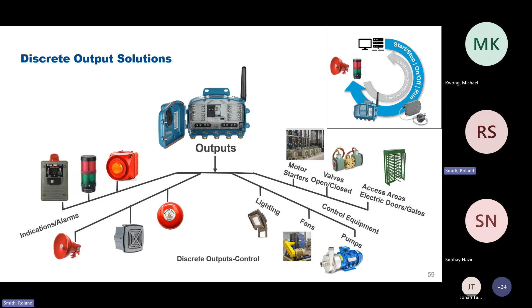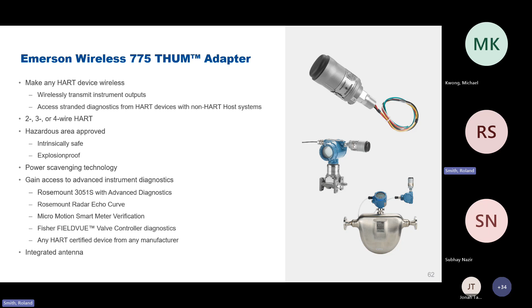We do have online corrosion and erosion monitoring, and a little bit on the THUM product. So a THUM is available as an option where a customer may have a traditional 2-wire loop-powered pressure transmitter, for example. We can install a THUM. It's loop scavenging, and we'll pull the HART variables off of that particular device, including diagnostics in some cases, depending on the device, and send it back to the gateway as well. So stranded diagnostics, radar curves, initiating some of our fancy things we do with Coriolis and our level transmitter can all be done wirelessly with the addition of that 775 THUM adapter.